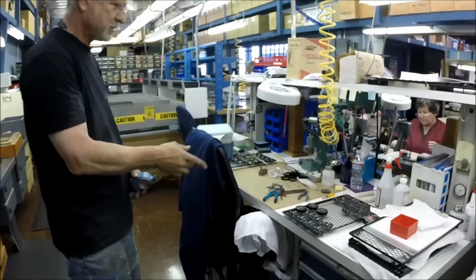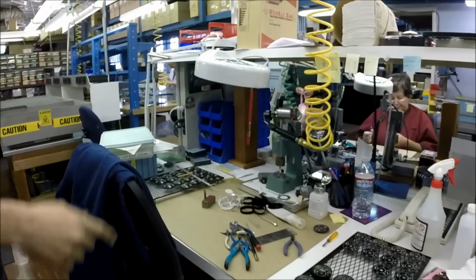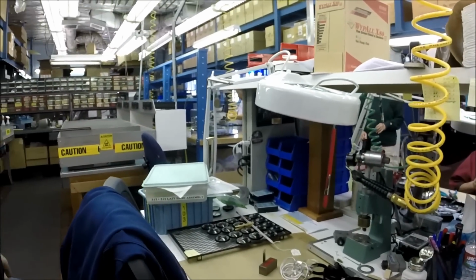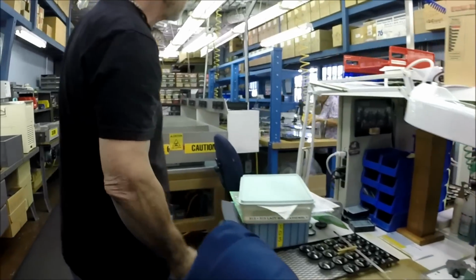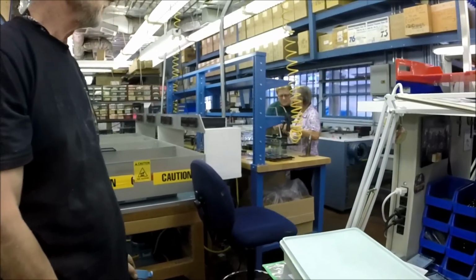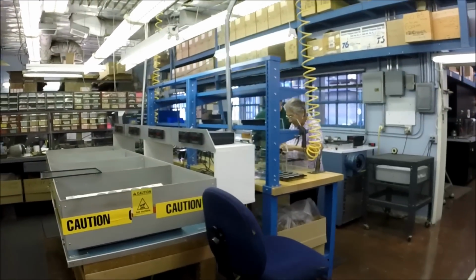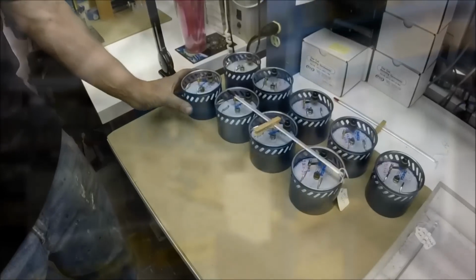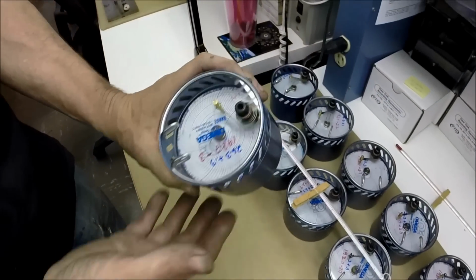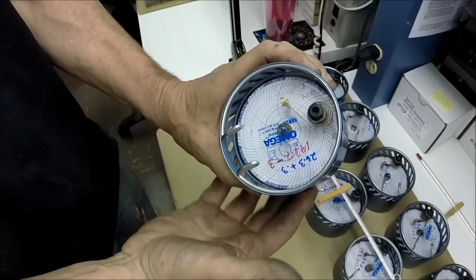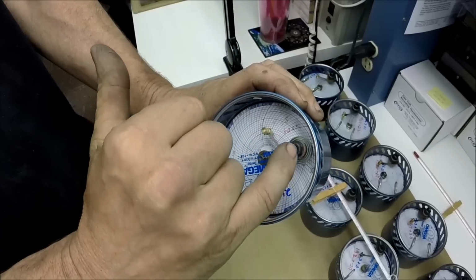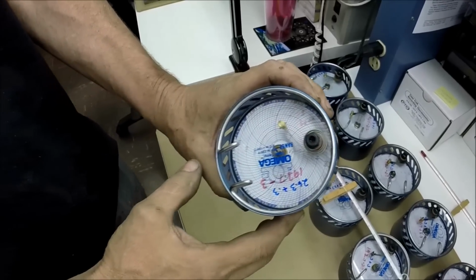This is more assembly of these, some private labeled thermometers. These are house labeled thermometers. And we're back to our calibration. These are chart recording thermometers. The chart is rotating. The stylus is moved up and down by the bimetal sensing element.